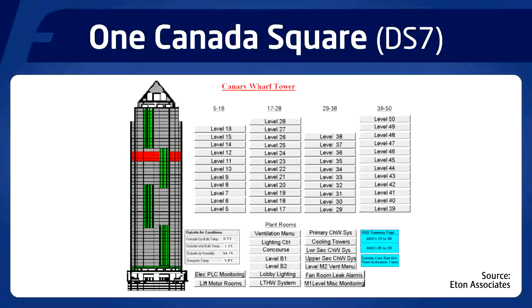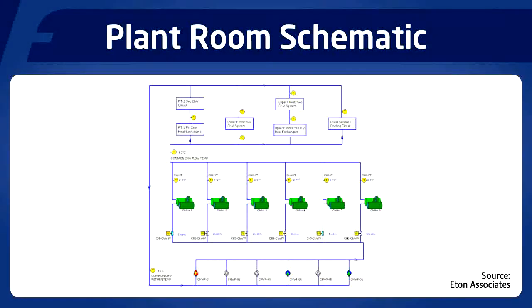We installed the pressure independent control valve on an air handling unit supplying cooling to level 6 of 1 Canada Square, also known as DS7. The chilled water system consists of 6 staged chillers and circulating pumps, and the particular segment or circuit that we are interested in is the lower floors chilled water secondary system.